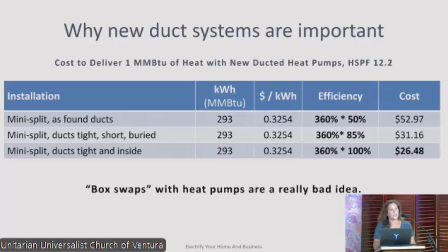The second scenario is where many of our ducts are, an inhospitable environment up in attics. When we still need to put ducts in the attic, we need to keep them tight, keep them short, bury them in extra insulation, and design them for the capacity of the heating and cooling system they're hooked up to. Then our losses get greatly reduced, to only about 15%.